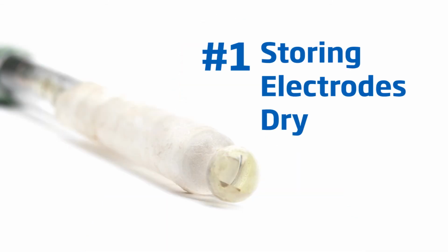Our top pH mistake coming in at number 1, storing electrodes dry. Have you ever done this? The buildup of salt on the electrode can get pretty frustrating, and you may not even know what's going on. This buildup coats the sensing glass, and eventually the glass becomes dry, slow to respond, and unstable. It takes a while to bring your electrode back to working order if it has been stored dry for a long time. But don't worry, there is a way to keep your electrode working.